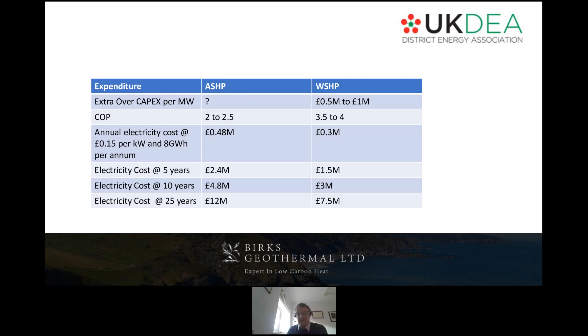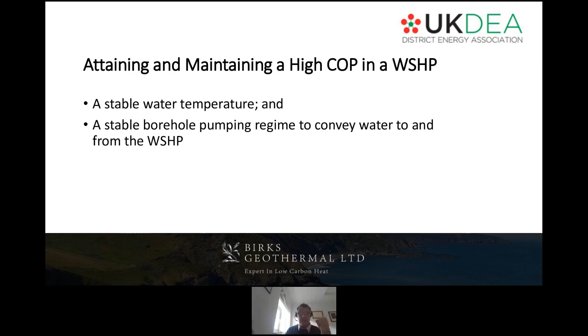And attaining and maintaining a high COP in a water source heat pump system, there are 2 things you've got to meet. One is a stable temperature, and that links back to, I think, Ken's presentation earlier. And the other is a stable pumping regime from the abstraction boreholes to the reinjection boreholes.